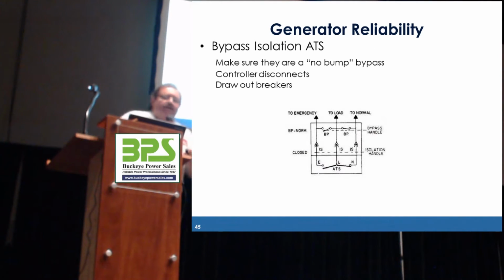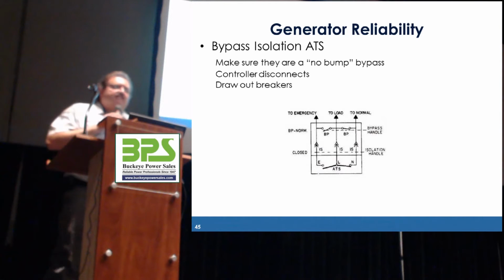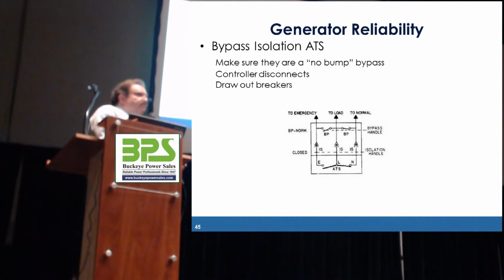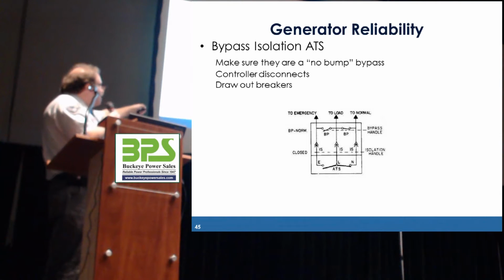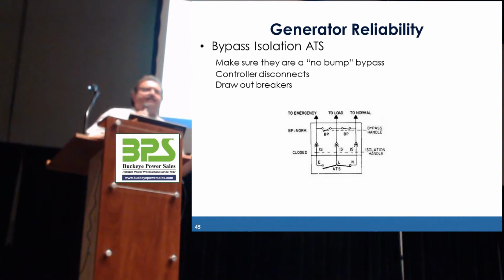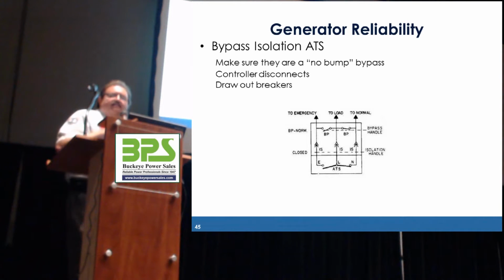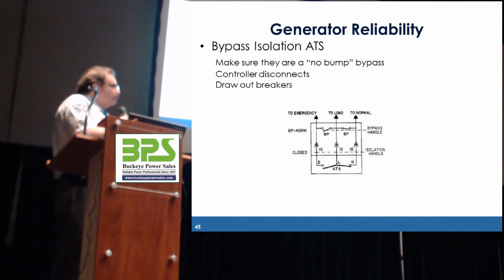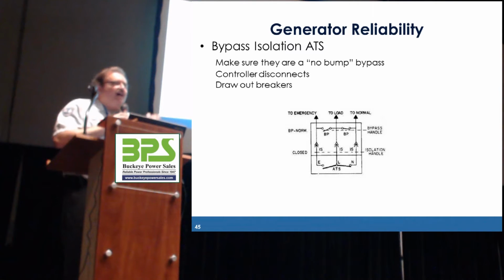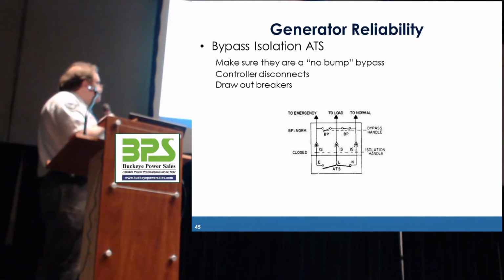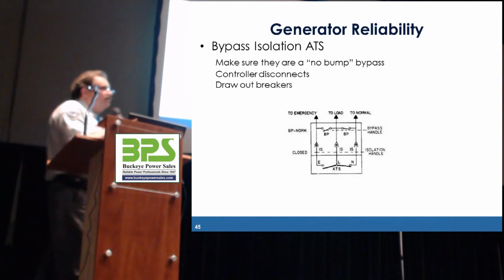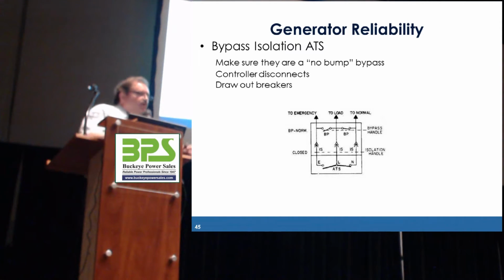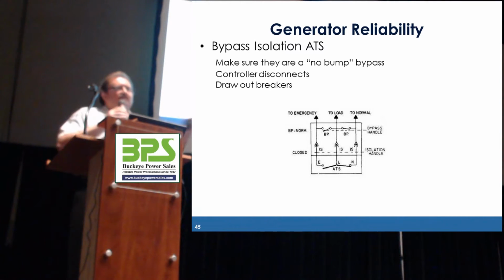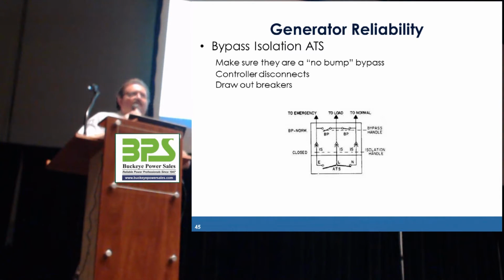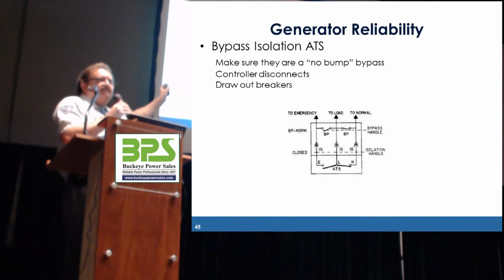Another thing that you can want to consider would be what's known as a bypass isolation transfer switch. This is a transfer switch with a series of another routing around it, just like your UPS has a bypass, a maintenance bypass. It has the same basic principle incorporated. So if we want to test the transfer switch and not affect the facility whatsoever, we can bypass the load to the utility. The transfer switch can rack out to a position where it can be tested electrically.